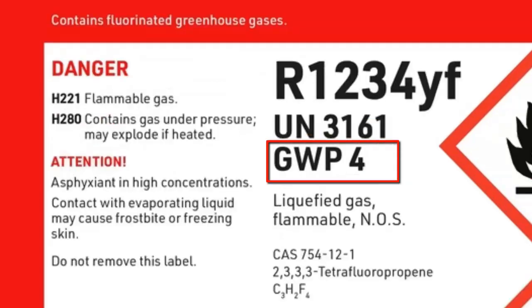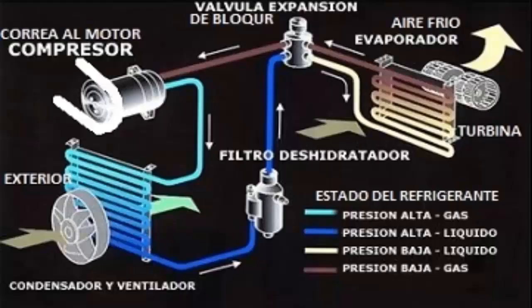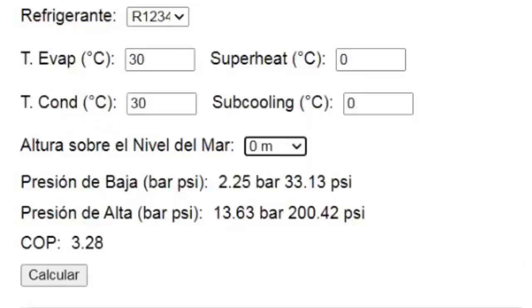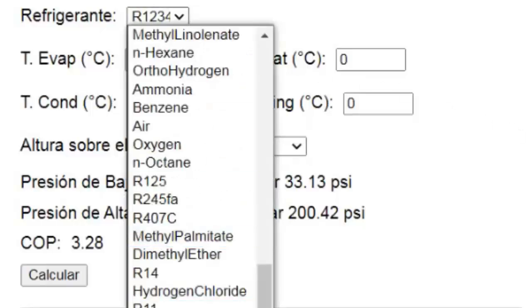Let's now observe the behavior of our R1234YF in the cooling cycle. Let's begin by selecting our R1234YF in the simulator. At this point, the AC system is turned off, so the temperature of the evaporator and condenser will be the same, and the pressure of the gas will correspond to the ambient temperature. In this example, we'll assume an outside temperature of 30 degrees Celsius, resulting in the following pressure values.